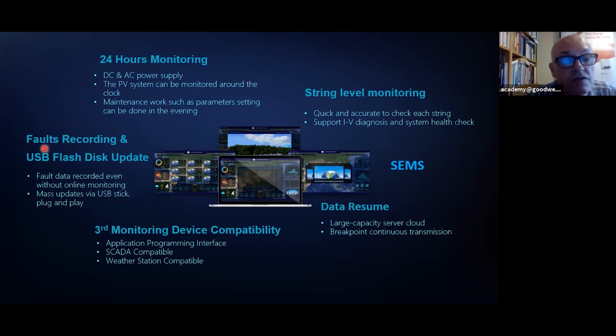You'd need to find out what's gone wrong with the inverter, and you need to be able to collect data. We can do that by plugging in a USB stick, downloading historical data from the inverter, and using that data to analyze what's happened.